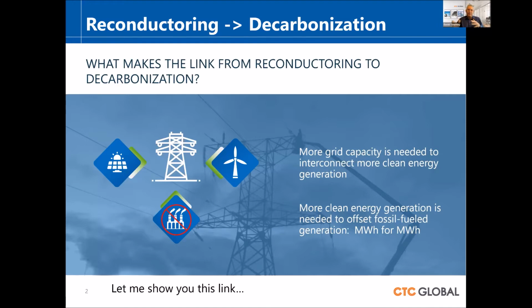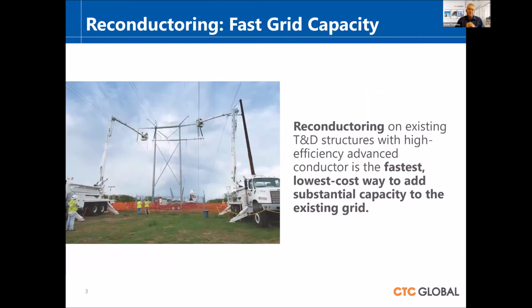So what makes this link between reconductoring and decarbonization? We need more grid capacity. There's over 800,000 megawatts of generating capacity that is in queue, meaning they have submitted applications, they've asked the utilities for interconnection. There's no grid capacity, or they're waiting for that capacity to be made available. So we need more grid capacity to interconnect more clean generation so that that generation can run offsetting fossil fuel generation on a megawatt hour for megawatt hour basis. What I'm going to tell you about is reconductoring on the existing T&D structures with high efficiency advanced conductor is the fastest, lowest cost way to add substantial capacity to the existing grid.